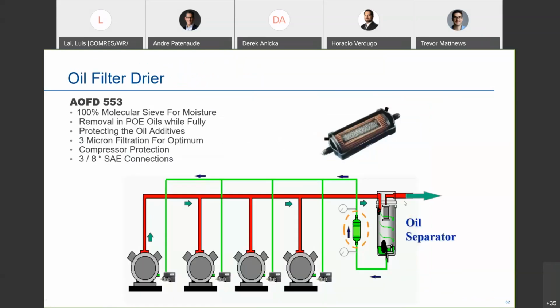Don't know if you were aware, but your oil needs to be filtered and dried. And as of late, we haven't talked a lot about this, but they're used on every single system. It may be a small part, but it's an oil line filter dryer that has 100% molecular sieve in the center. It has no activated alumina that can strip acidic POE additives. Additives that we put in oil on purpose.